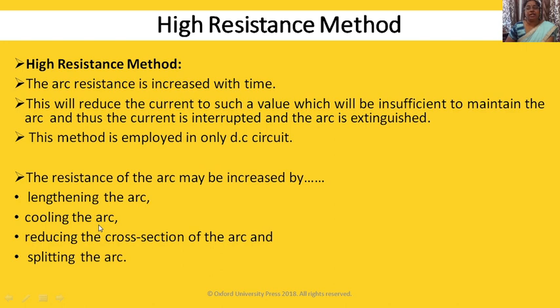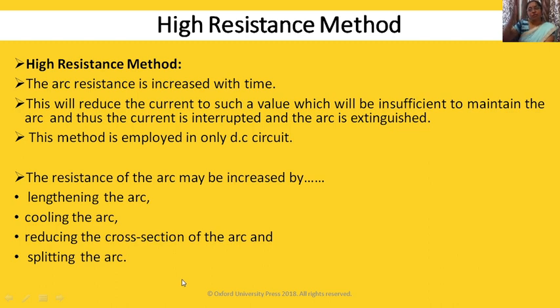The second method is cooling the arc, which will deionize the medium. Then, reducing the cross section of the arc: R = ρL/A — if you reduce the cross-sectional area, resistance will increase. And then splitting the arc — if you split that arc column with the help of splitters, resistance gets increased.